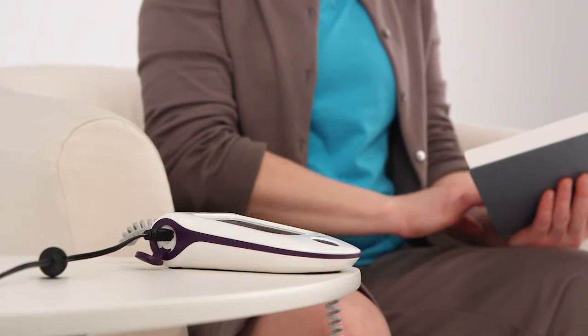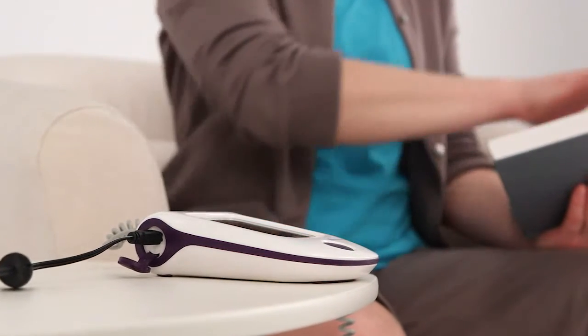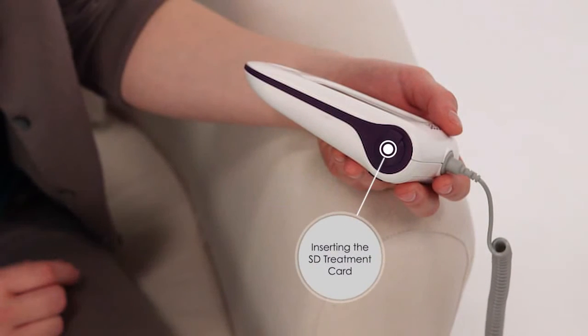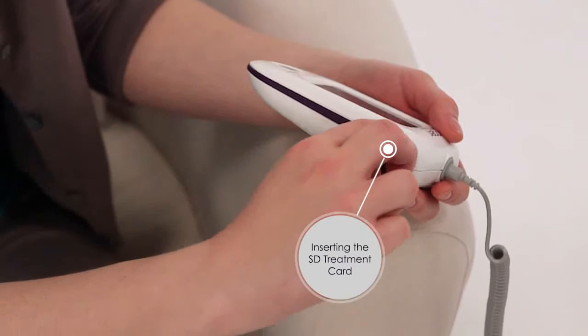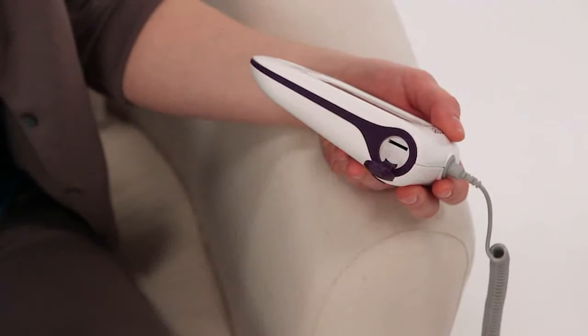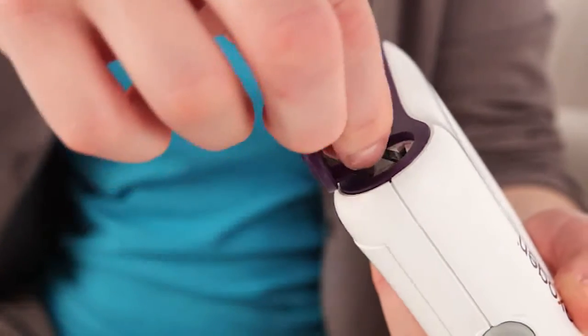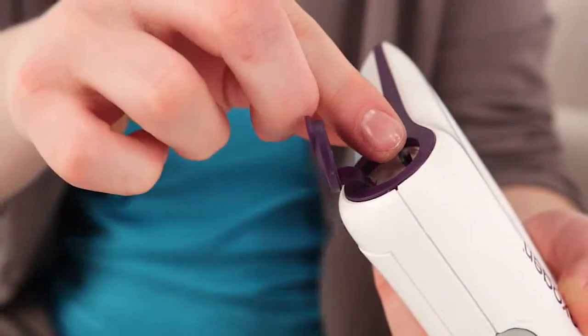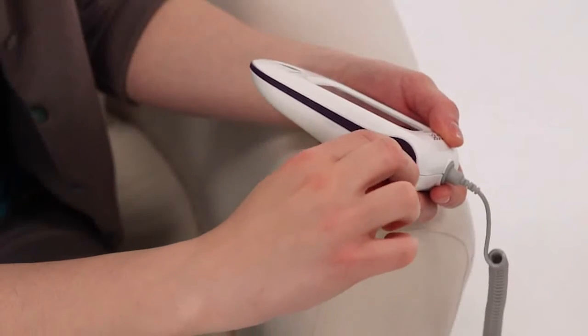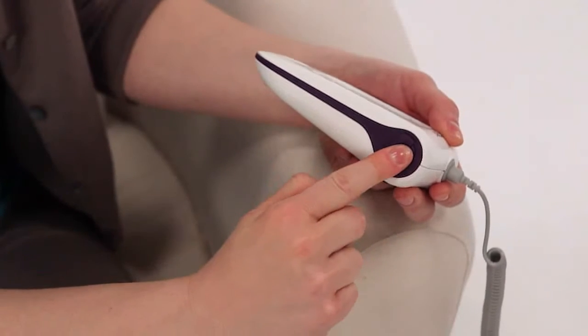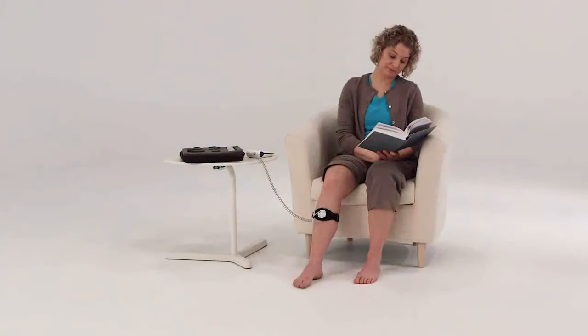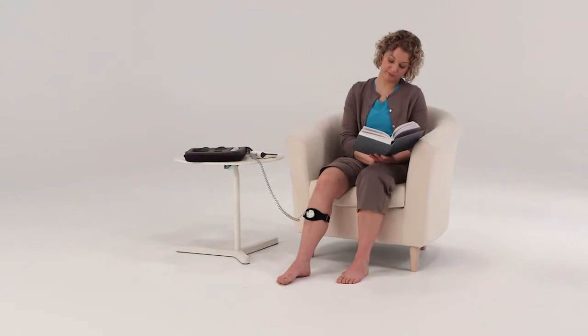After the initial charge, you can recharge your device whenever it is convenient for you, even during the Exogen treatment. After you've charged the battery, open the SD cover on the right side of your Exogen device by pulling down on the tab. Insert the SD treatment card into the SD port with the metal contacts facing up and entering first. Press the card into the port until it clicks into place and close the cover. The card should stay in the device until your course of treatment has been completed.